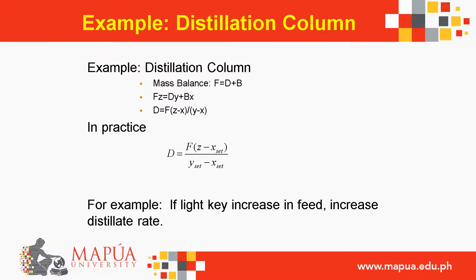Another example — distillation column mass balance: F = D + B, F·z = D·y + B·x, so D = F·(z − x)/(y − x). In practice, D = F·(z − x_set)/(y_set − x_set). For example, if the light key increases in the feed, the distillate rate will increase.